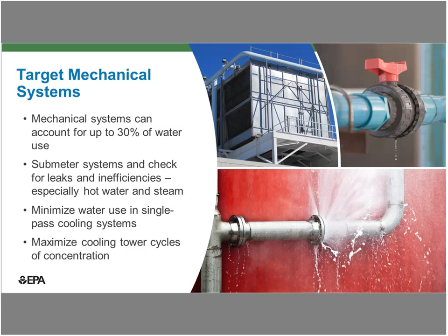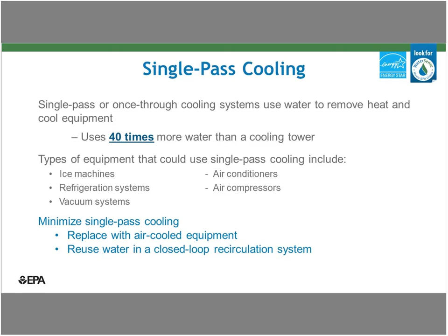If you have any single-pass cooling system, you want to really try to eliminate that whenever you can, because it is really wasteful, and you want to maximize the number of times your cooling tower cycles water. Single-pass cooling basically just uses water once to cool the piece of equipment, and then it goes down the drain. That takes about 40 times more water than a cooling tower would to cool the same heat load. It's incredibly inefficient. All types of equipment can use this, so you may want to look at them and see if there are air-cooled options, or an option to recirculate the water to use it multiple times before you discharge it to the sewer.